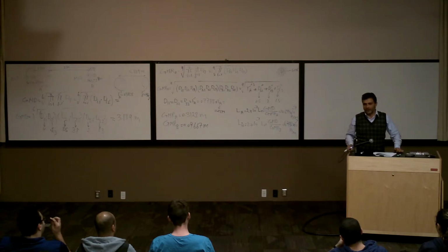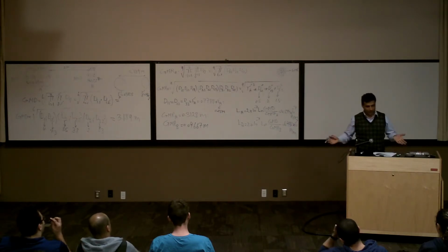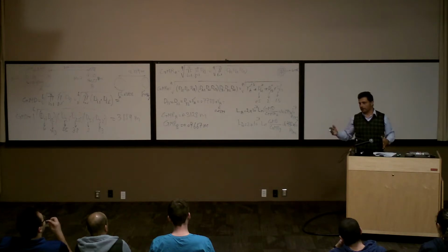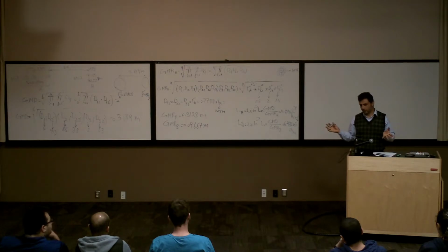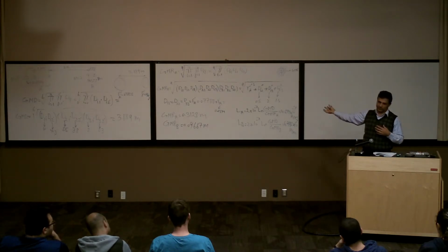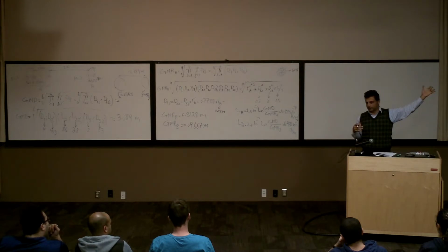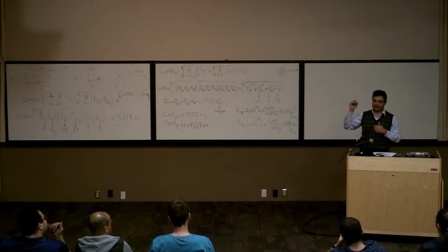Before getting there, we have a 3-phase system, right? We want it to be balanced. We want LA, LB, LC to be equal, right? We don't want a transmission line where, for example, LA is 200, LB is 100, and LC is 300, right? We don't want that. Why? It's going to make an unbalance in the system. For example, we have a generator generating a balanced 3-phase voltage. But because we have different values for each line, at the end it's going to be 3 different things. It's not going to be balanced anymore. So we like to keep LA, LB, LC the same.